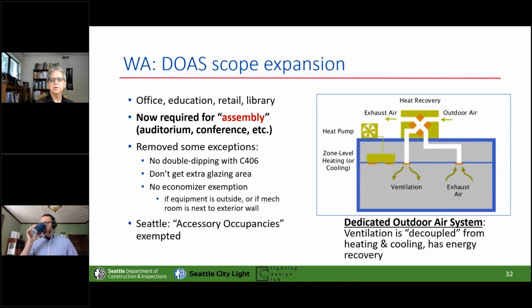You've just been hearing about DOAS, dedicated outdoor air supply. That applies to office, education, retail, library, right? That in the current code has expanded now to include most assembly occupancies. A DOAS works well for assembly, and some of the exceptions that had been in the previous code, where you got some freebies for using DOAS, have gone away.